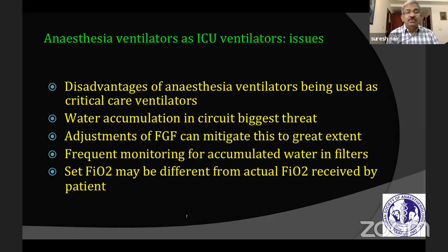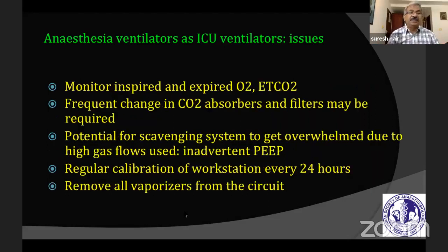One, you have to look for water accumulation in the circuit. It also alters the set FiO2 because you have two things: the expired gases coming back, plus you're adding fresh gas flow from outside. Together, we don't know what FiO2 is actually being received by the patient. Second, frequent changes of carbon dioxide absorbers are required, especially if too much water accumulates in the circuit.